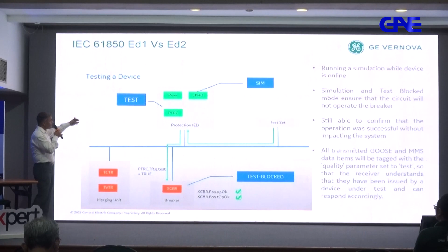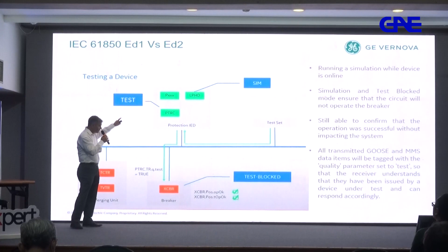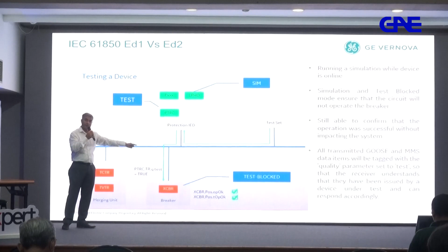So that's the overall scheme. So you put your protection IED in a simulation mode to begin with. You want to test any function, you put that function in a test mode. When you come to merging unit, you put the merging unit in a test blocked mode so that it does not operate the output actually, but still you will be able to monitor the attribute. So this is how you can perform the testing when you are online.